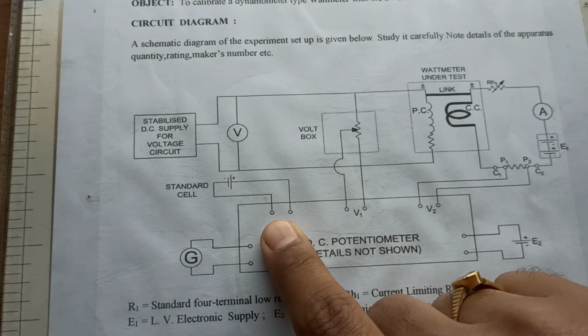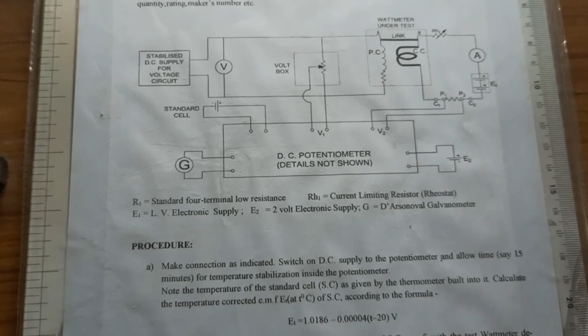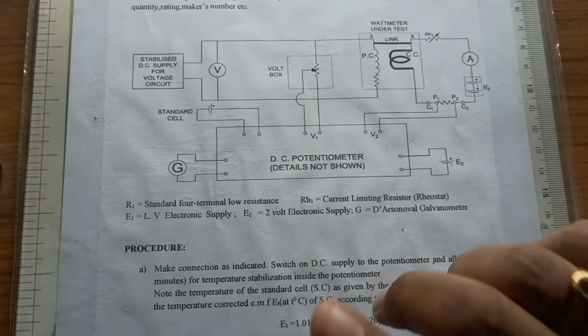And here is a standard cell connected in it. We will use this standard cell voltage to standardize the potentiometer based on this EMF when the wattmeter is in a de-energized condition. And here is the supply for this DC potentiometer.